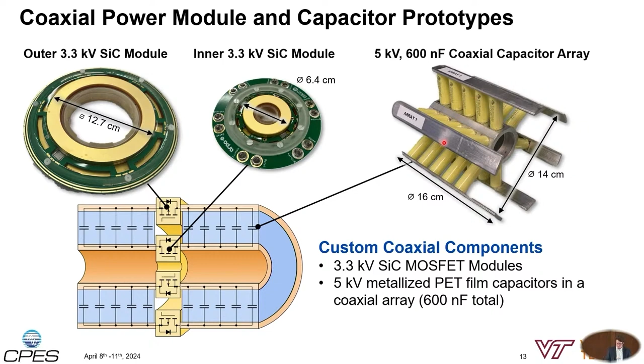So here's a look at some of the hardware. These are the 2 coaxial silicon carbide modules we built. You can see the smaller one and the larger one. These nest within each other, along with the coaxial capacitor array. You can see the high voltage contact here at the center, and that current spreads out radially with the lower voltage contacts around the outer circumference.